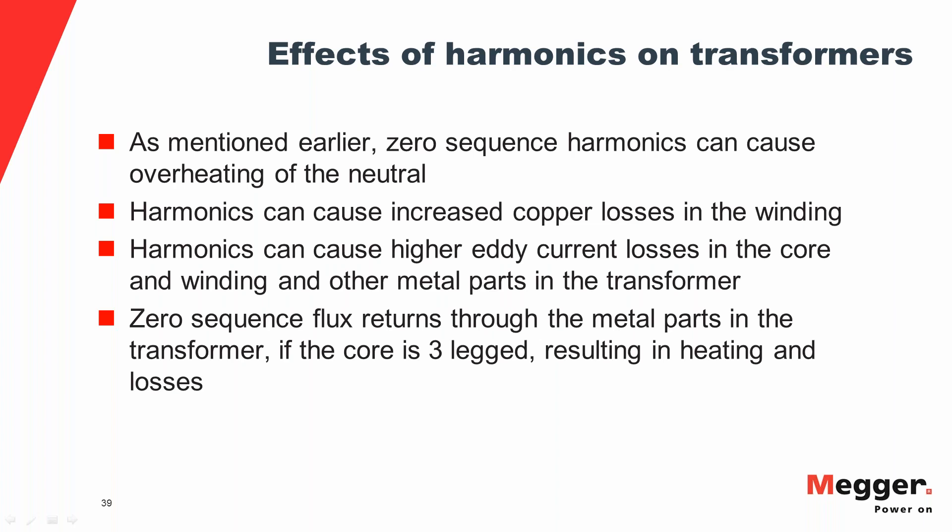Larger transformers usually have a five-leg core with three winding legs and two auxiliary limbs; smaller transformers have three-leg cores. When zero-sequence currents are present, zero-sequence fluxes are generated in the core and need a return path. In a three-leg core, the only return path is through the structural metal parts of the transformer — parts not designed to handle flux flow — causing significant heating and deterioration. Zero-sequence fluxes can therefore cause serious problems in three-leg core transformers.